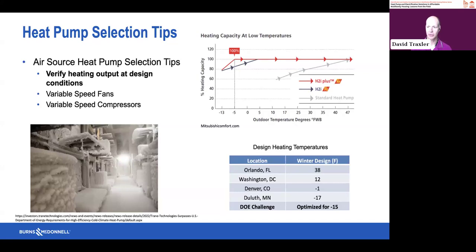But then as it got colder, you get down to the teens, the capacity drops off significantly. And the colder you get, the heat pump cuts off altogether. And then you go to electric resistance, or you go back and forth. So with high heat output, cold climate heat pumps, you get much more heating at colder temperatures. And that's what this graph is showing: you can get full heat pump capacity down to 7 or 5 degrees, or even down to -5 degrees, depending on your unit. And so that's a big thing also.